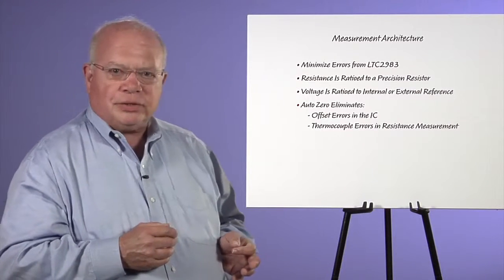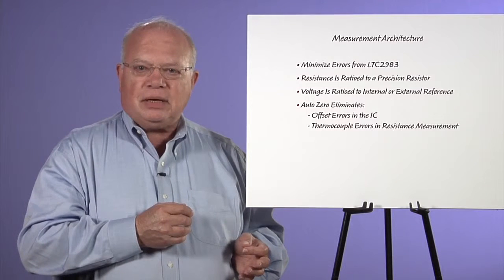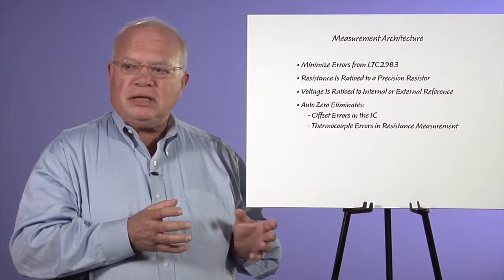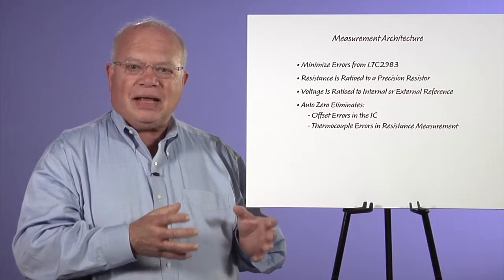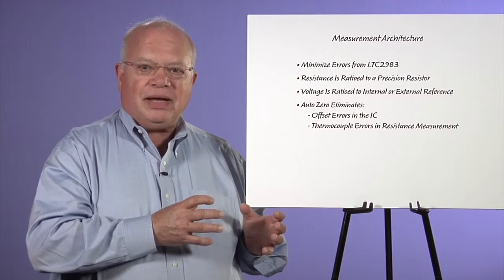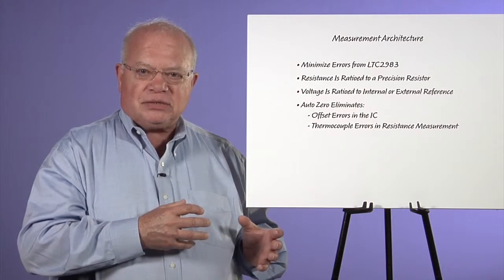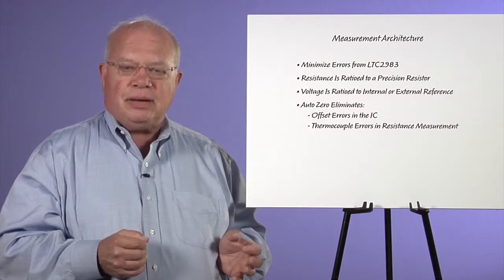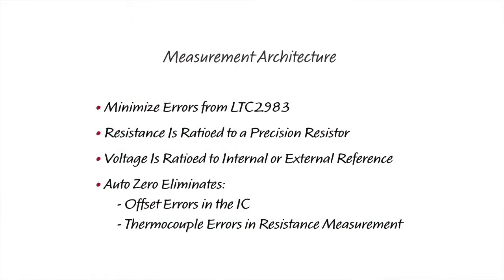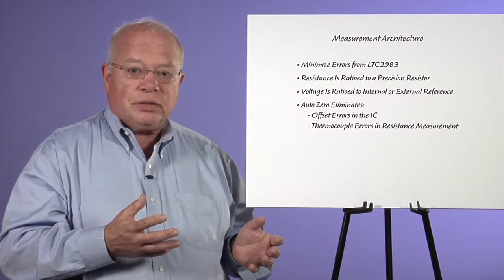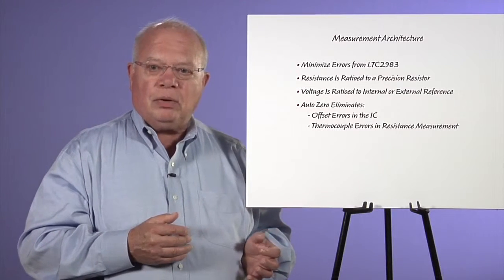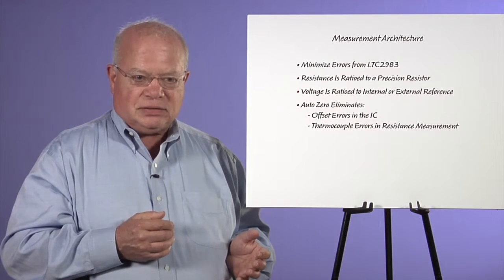The measurement architecture of the LTC 2983 is to try to minimize the errors in the electronics. We're trying to get the best accuracy and conformity we can get between the input from a sensor to an output in digital temperature. So we've got architectures that try to minimize these errors. With a resistance sensor, you have to reverse the sensor current periodically, or else you'll get thermocouple errors from the sensor because the wires in the sensor generate thermocouples. You also have to keep the power low in the sensor, or else you'll have self-heating effects.